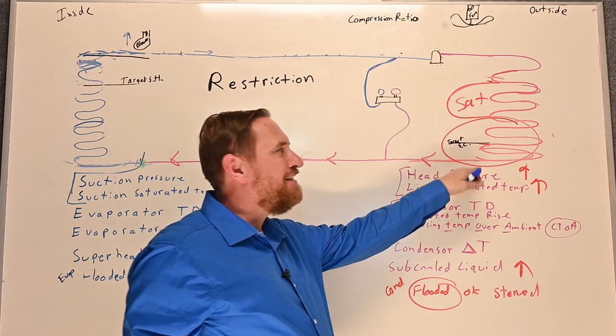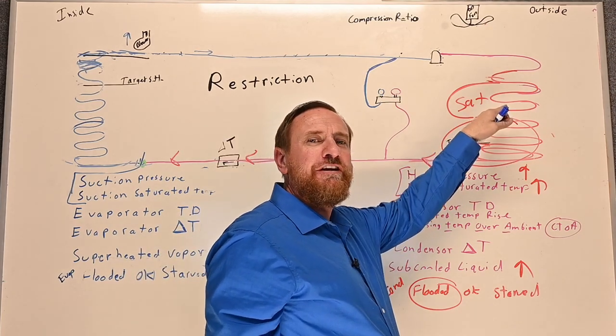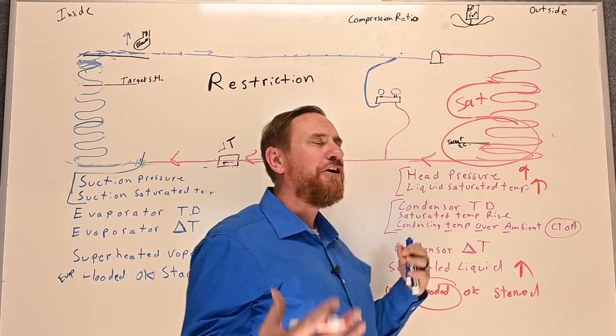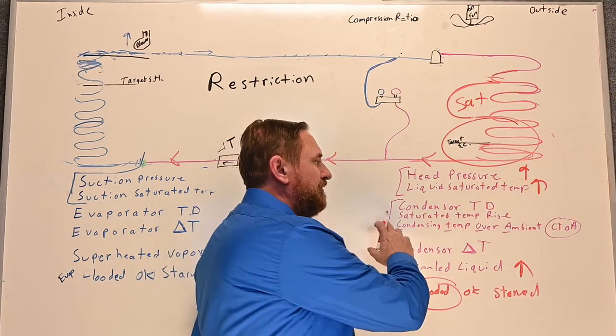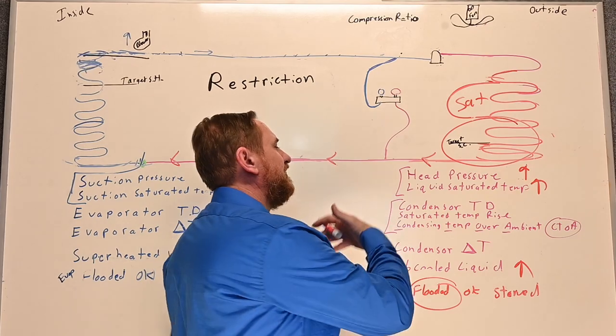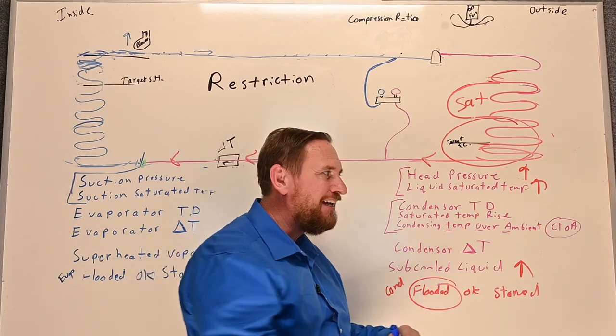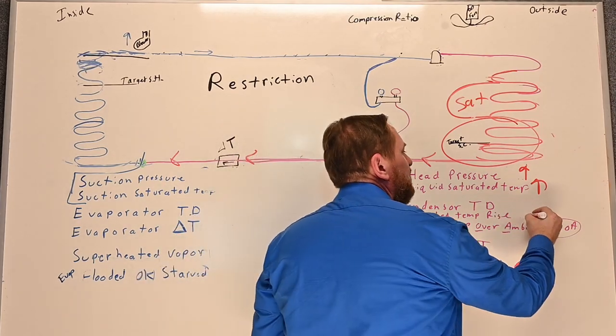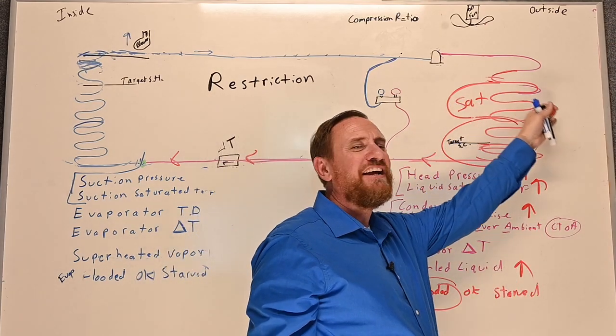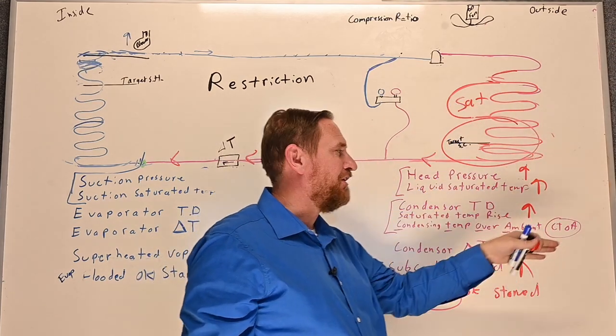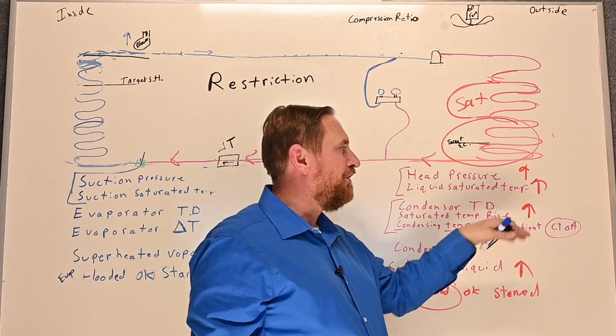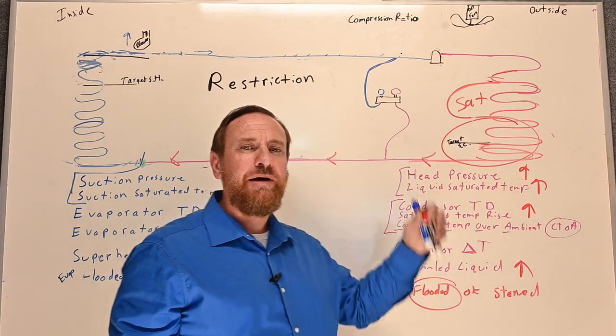The saturation has to transfer all that heat and change state from vapor to liquid in a much smaller area. The only way to make that happen is with higher pressure. So our pressure goes up, and our saturated temperature goes up to transfer heat in that smaller area. Because the saturated temperature goes up, the temperature difference between the refrigerant and the air gets much larger — the condenser TD, also called CTOA or condensing temperature over ambient, also increases. This is what you call high head pressure.